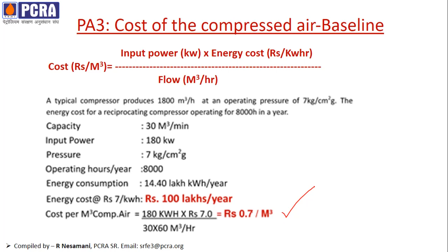A sample is available for a compressor of capacity 30 meter cube per minute with input power of 180 kilowatt. The calculated cost of 1 meter cube of compressed air is 0.7 rupees. So the purpose of calculating is that this is a baseline. After doing various methods and various improvement strategies, we have to calculate again so that it should come down, so that we can have a comparison.